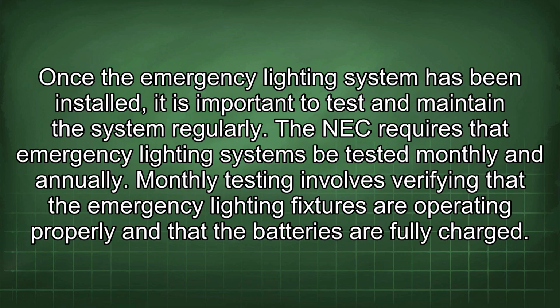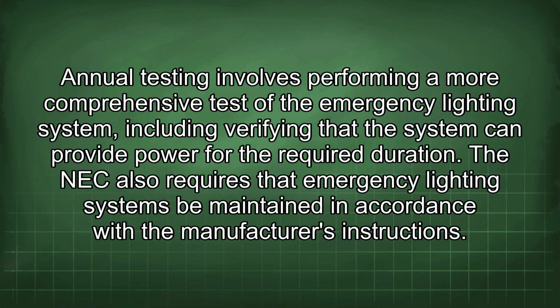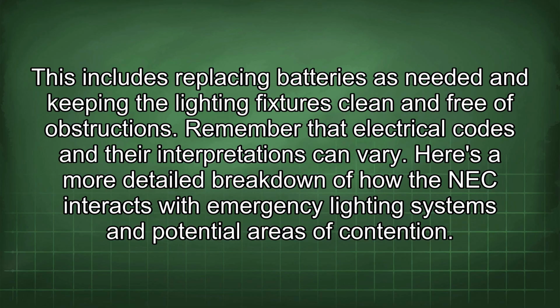Once the emergency lighting system has been installed, it is important to test and maintain the system regularly. The NEC requires that emergency lighting systems be tested monthly and annually. Monthly testing involves verifying that the emergency lighting fixtures are operating properly and that the batteries are fully charged. Annual testing involves performing a more comprehensive test of the emergency lighting system, including verifying that the system can provide power for the required duration. The NEC also requires that emergency lighting systems be maintained in accordance with the manufacturer's instructions. This includes replacing batteries as needed and keeping the lighting fixtures clean and free of obstructions.